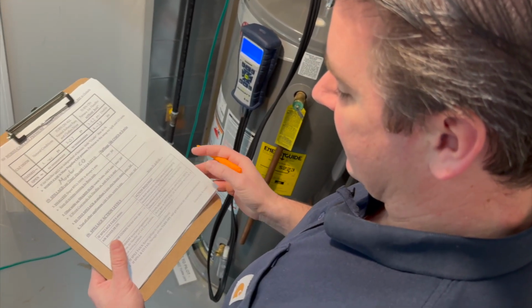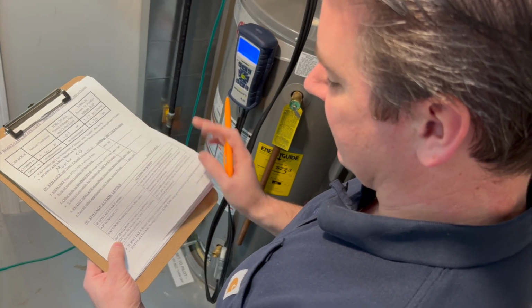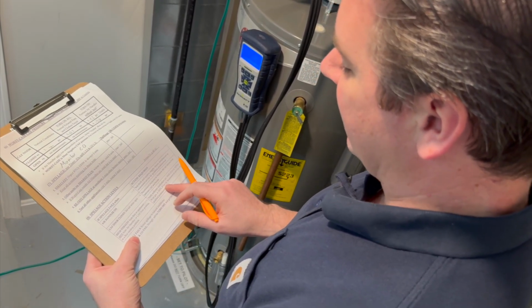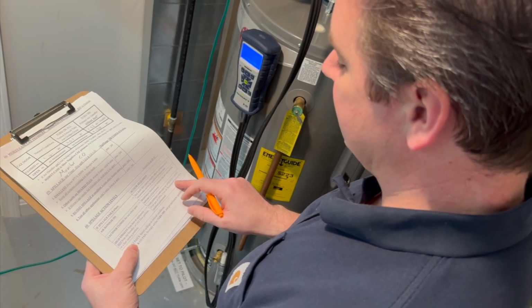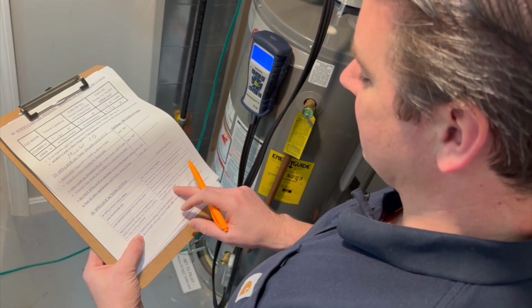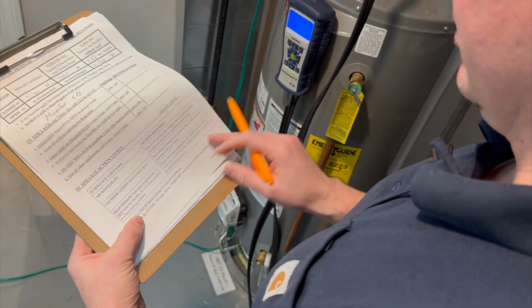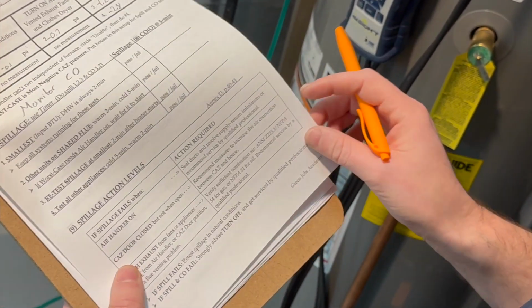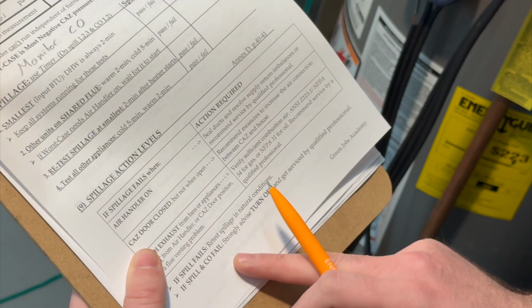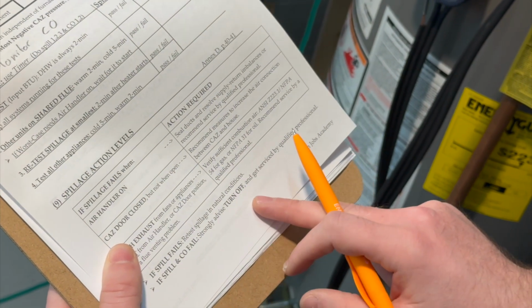And if it fails when the high exhaust from fans or appliances, but not from the air handler or CAZ door position or a flue venting problem, verify sufficient combustion air according to ANSI Z223.1, NFPA 54 for gas, or NFPA 31 for oil. Recommend service by a qualified professional. If spillage fails, retest spillage in natural conditions. And if spillage and CO fail, strongly advise the homeowner to turn the unit off and get a service by a qualified professional.